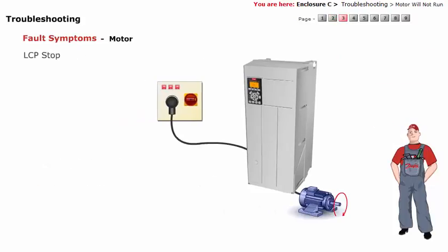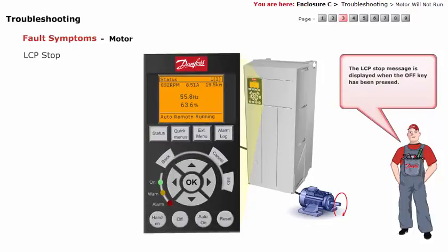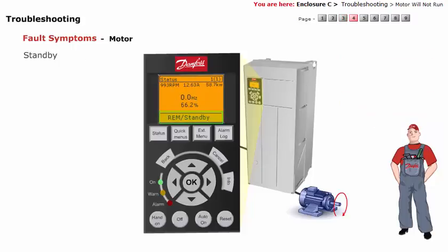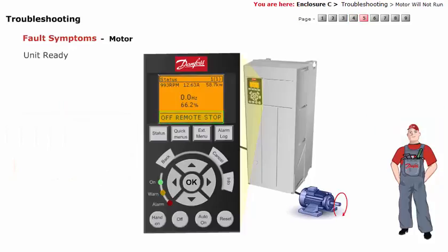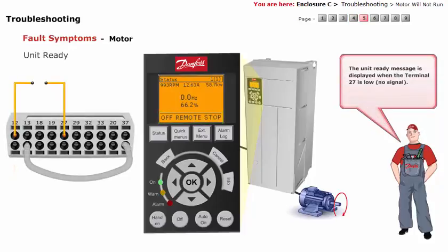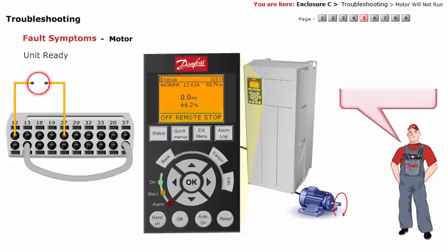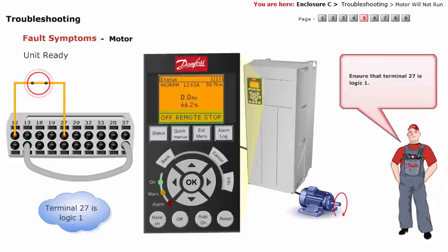LCP Stop: The LCP Stop message is displayed when the off key has been pressed. The bottom section of the display will also be flashing when this occurs. Stand By: The standby message is displayed when there is no start signal at terminal 18. Ensure that a start command is present at terminal 18. Unit Ready: The unit ready message is displayed when terminal 27 is low — no signal. Ensure that terminal 27 is logic 1.